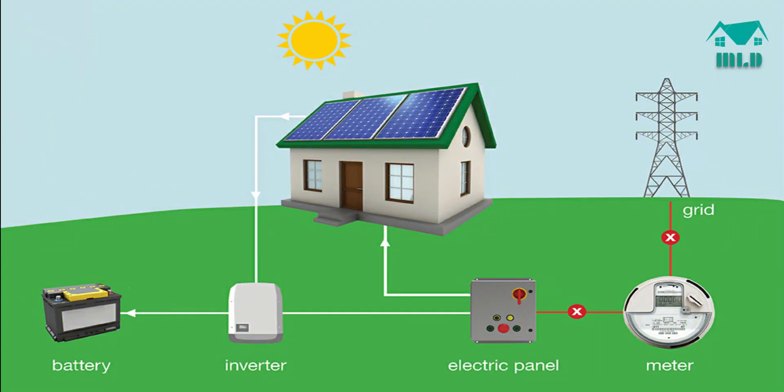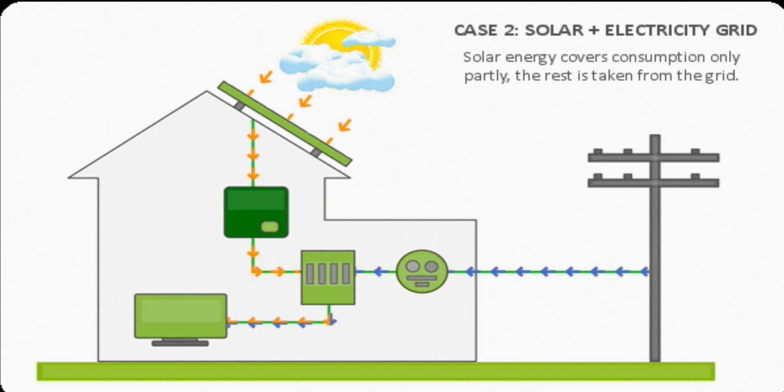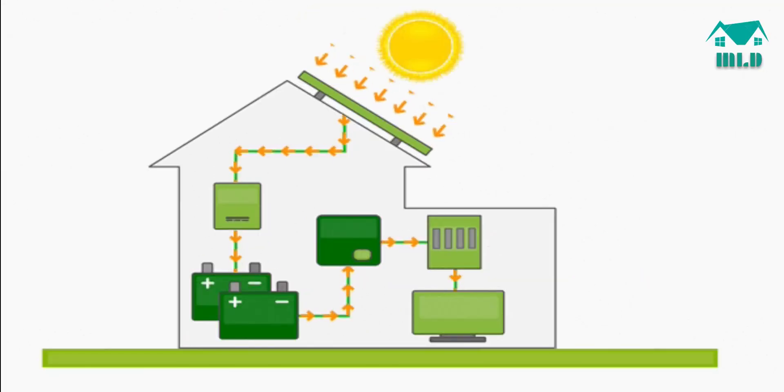There are different built-in modes in a hybrid inverter. For example, on a sunny day from 9am to 5pm, the inverter gets power from the solar panel as a primary source and operates the load. If the solar panels are producing more than the requirement of the load, then the excess power will be exported back to the grid at the same time. If at some instance the production from solar panels gets reduced or the load requirement gets increased, then the inverter will decide to get the remaining required power from the utility grid as a second source. We can also choose either the utility grid or batteries as a secondary source.